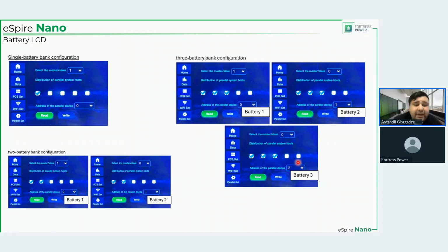Now, this is very important. If you need to see what was entered from the factory, or what you have entered, and you want to check it, you click read, right? Once you select those settings, if you don't tap write, it's not going to acknowledge the settings. So you tap write once you have configured the settings, and then if you do read, it's going to show you the settings that you have entered. If you don't tap write, and you just click read, it will just show you the original settings, right? That type of thing. So read and write, please be mindful of that when you are working with the batteries and trying to configure them.